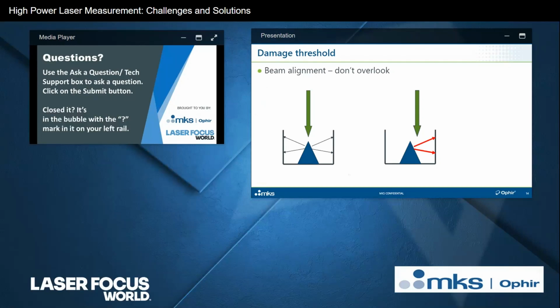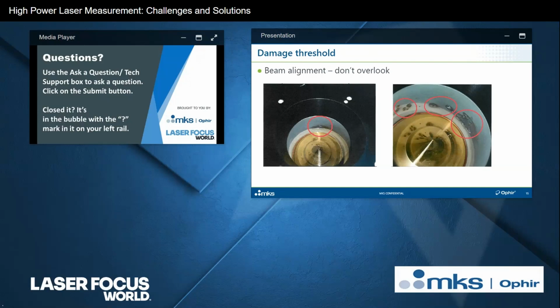Instead of being deflected in a full 360 degrees with a divergence angle, it's only going in one direction, which means that beam is being spread out over much less surface area than I might have thought, which means that the surface area that is getting the beam is getting a much higher power density than it's supposed to. And here you can see one of the possible results of that. When we get a sensor in for repair that's been damaged, and we see one of these reflective cone type sensors, and we see burn marks in specific areas, we're pretty sure that that is what had been going on there. Localized damage because one region of that cylindrical absorber wall was getting all of the power, which means much higher power density than it was supposed to be getting.